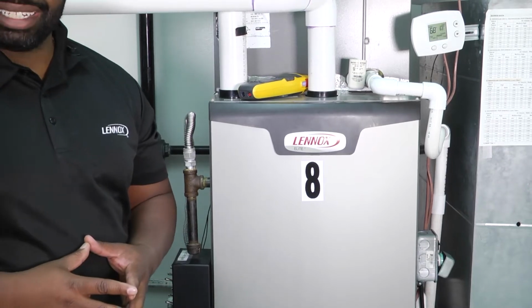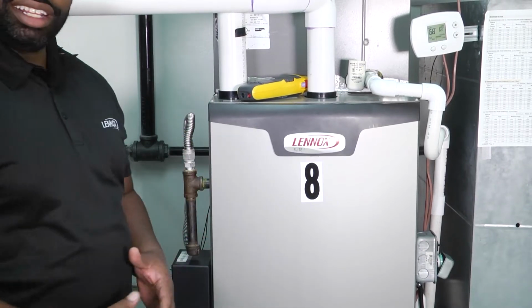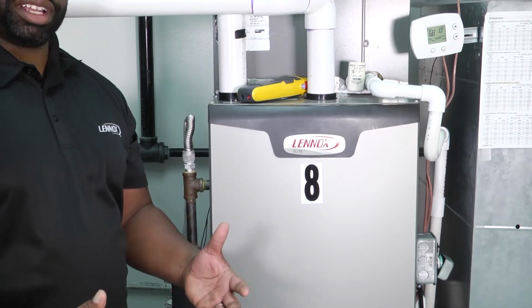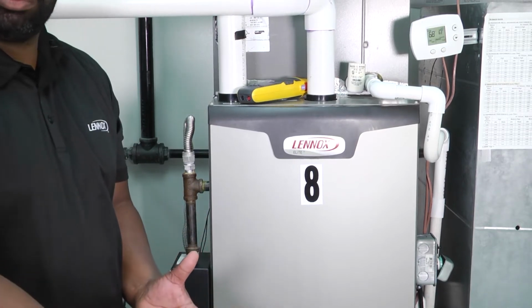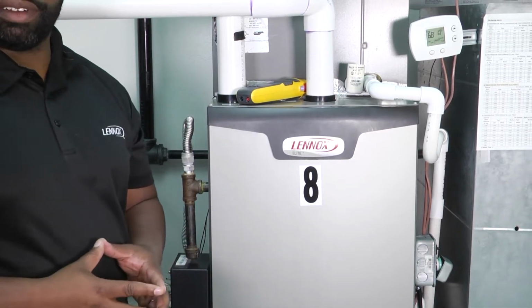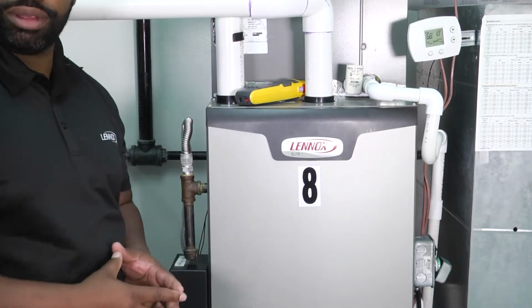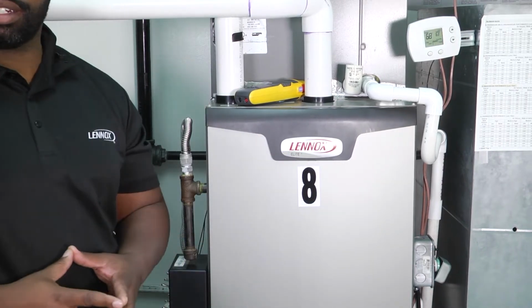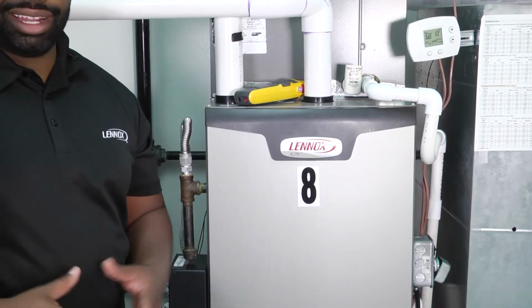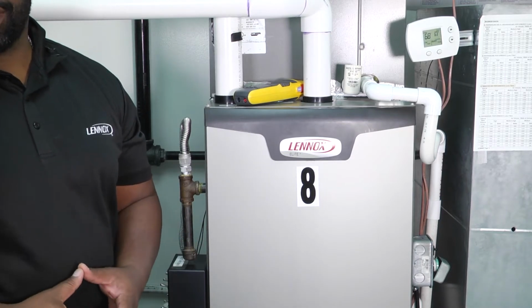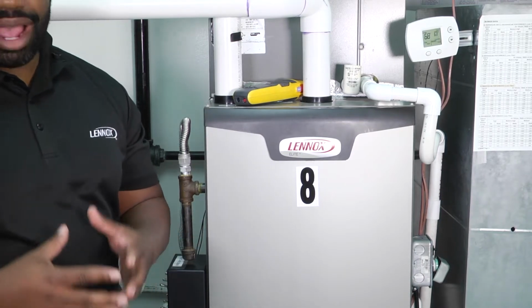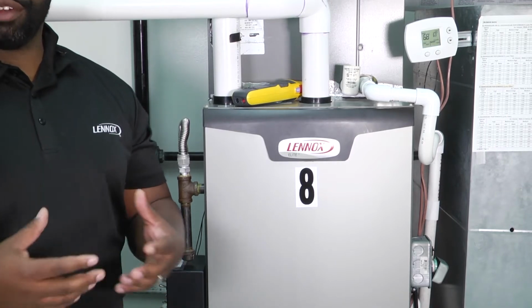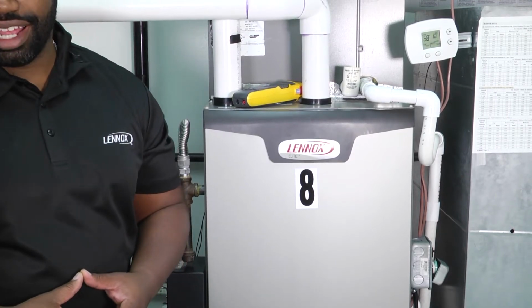So what that means is when we're doing our checks, technicians in those regions may have to actually pull the blower motor or use a device, a scope or something like that, to look inside and see the heat exchanger. Well, in an attic that's 120 plus degrees, pulling the blower motor might not be on your list of favorite things to do that day.